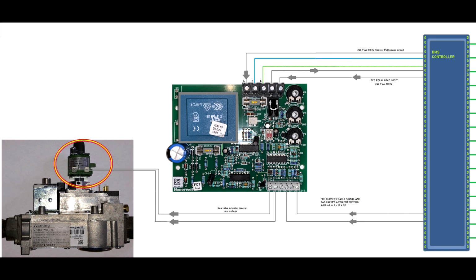But I just want you to understand, this is not the main gas valve. So if the burner will not open the main gas valve, it doesn't matter what this printed circuit board does moving this actuator. There won't be gas through this gas valve at all. So what you will see here is just a low voltage control capacity, and has nothing to do with the safety, because if the main gas valve will be closed, it doesn't matter how you will actuate that feature, there won't be gas at all through this gas valve.